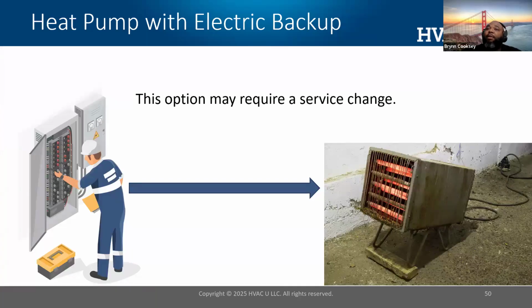When you do this type of setup, it may require a service change, where the service for my customer's premises may now be inadequate to accommodate the heat pump. So I may have to increase that service to accommodate the heat pump and my electric heat strips.